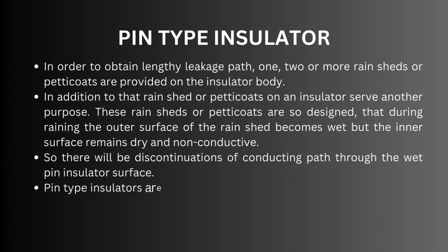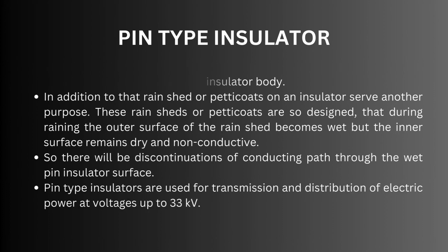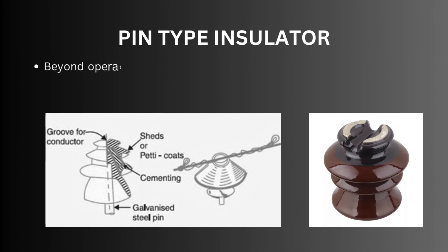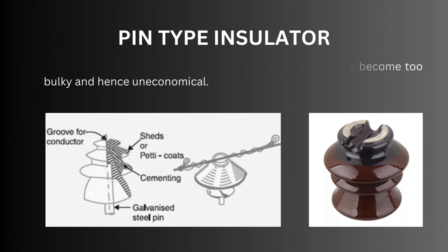Pin type insulators are used for transmission and distribution of electric power at voltages up to 33 kilovolts. Beyond an operating voltage of 33 kilovolts, the pin type insulators become too bulky and hence uneconomical. The figure below illustrates a pin type insulator.